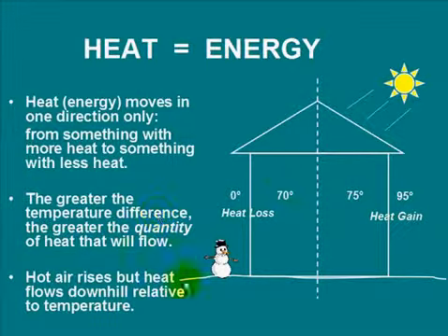So I want you to understand this. Don't think, oh, I'm in an attic and I've got to bust up the frame to get low in the outside wall. It's not necessarily a requirement, especially when you're on a second floor. Don't worry about supplying heat from overhead in a cold climate, because you've got the whole downstairs heating situation that's rising to the upstairs. By convection, the hot air will rise and warm those second floor floors on the way up.